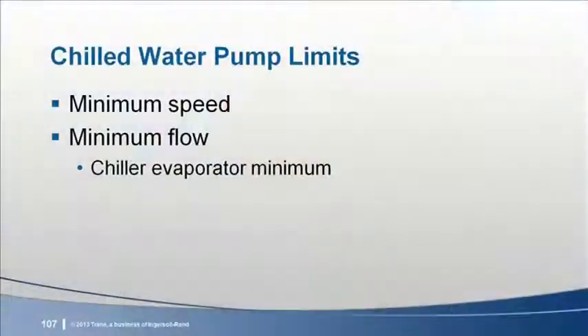Finally, the chilled water pump variable speed drive has a minimum speed. Also, the chiller evaporator has its minimum flow rate. The system and its control must provide a method for flow to remain above that minimum flow rate. We've discussed this in previous E&Ls on variable primary flow, and there are many system operations that result in component limit violation. We'll take the time today to cover two system limits.